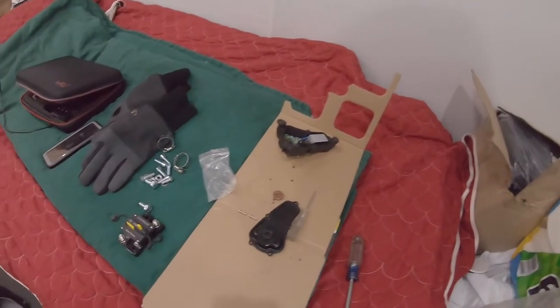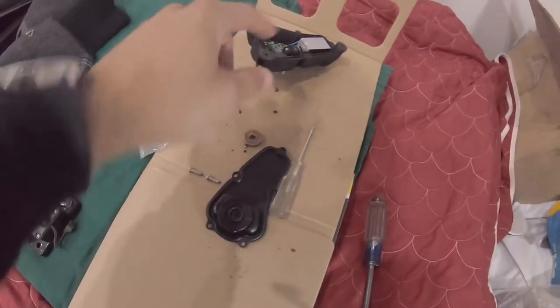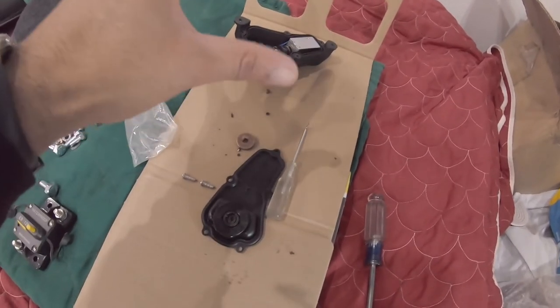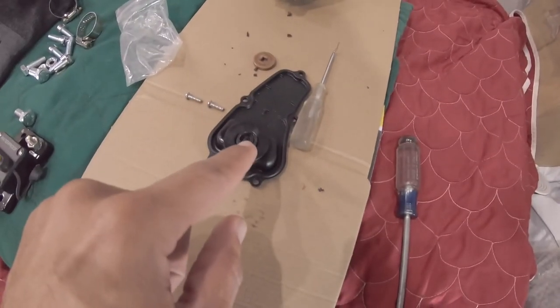So that, and then the isolator also, this is like trash. It's not trash. If I could order this mechanism right here, I could refurbish this. This is still perfectly good. It's operational. But just the little plastic piece that rotates this disc, it just melted or snapped. It just got overused, too hot. So I could try to reach out to see if I could get that part alone, and I could refurbish that, and then I could sell it or get rid of it or whatever, because it's still good. Everything electronically about the system setup, it works. I think I just have too much juice flowing through that isolator where it was just too much for it to handle, and it just burnt up.